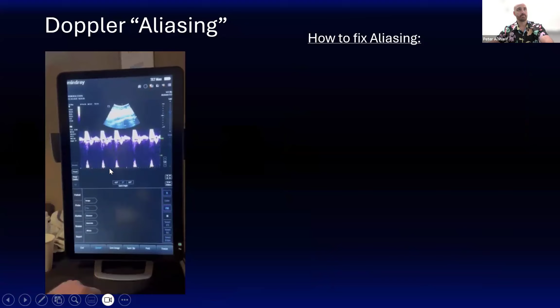So here we've got an example of some aliasing on Doppler. One thing you can do is change the scale of the Doppler. By pinching or opening your fingers, usually pinching, you'll make that whole waveform smaller. And this is not just zooming in and out. This is changing the way the machine shoots sound waves out, by changing the frequency of sound wave emission.